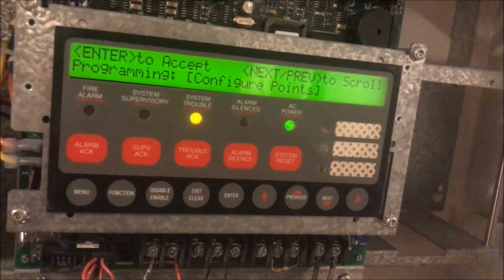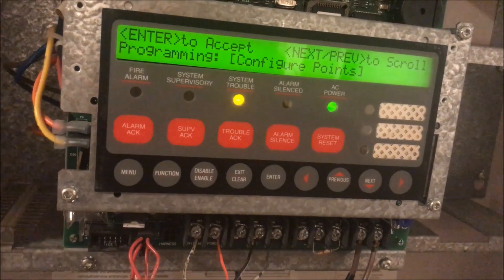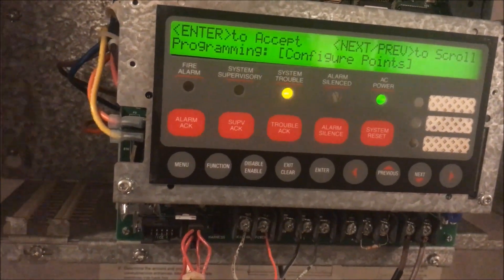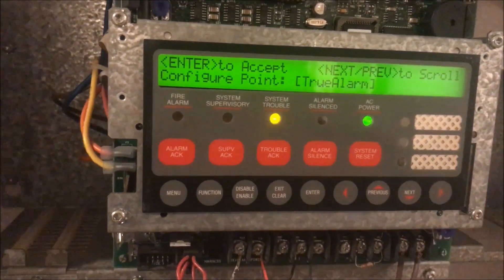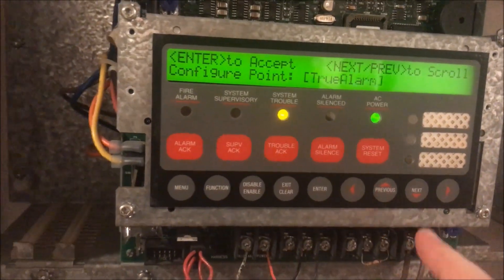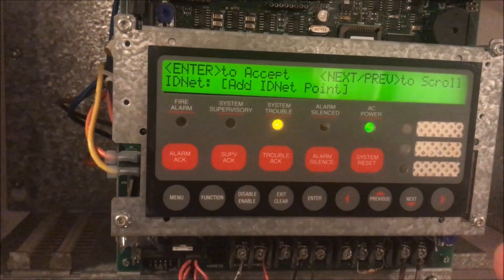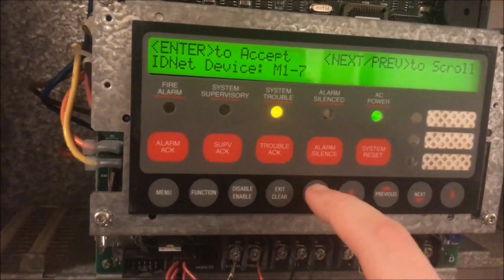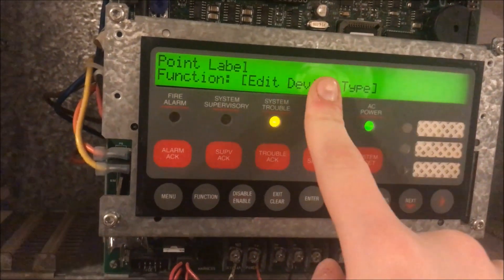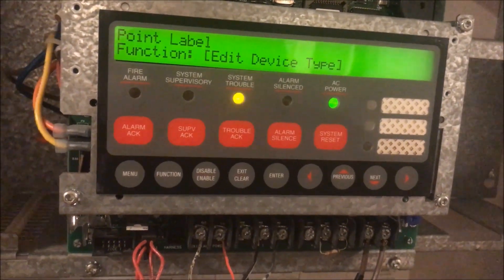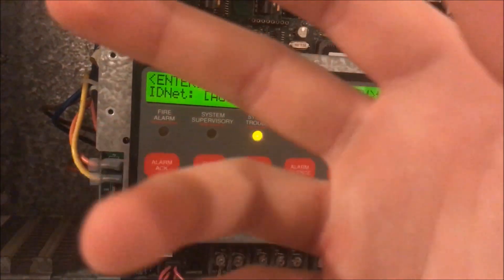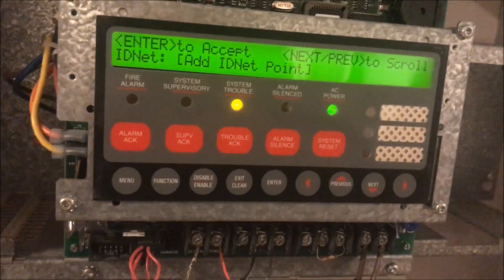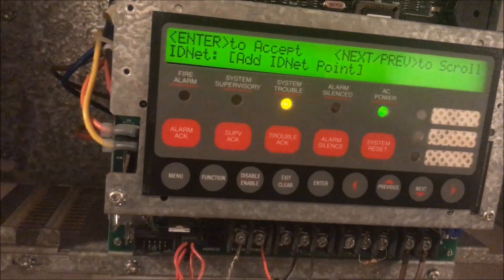The main thing I'm covering in level four is programming — in level four you can actually add, edit, and delete points. Hit enter and you can navigate: adding a pull station goes under one submenu, adding a smoke detector goes under another. Go to Pull Stations, then Add IDNet Point, and it gives you a list of your next available device. You set the device type, the point type, and the point label, and when done it asks: restore configuration, exit without saving, or save configuration. You'll want to save, and the panel will do a cold start to apply your settings.